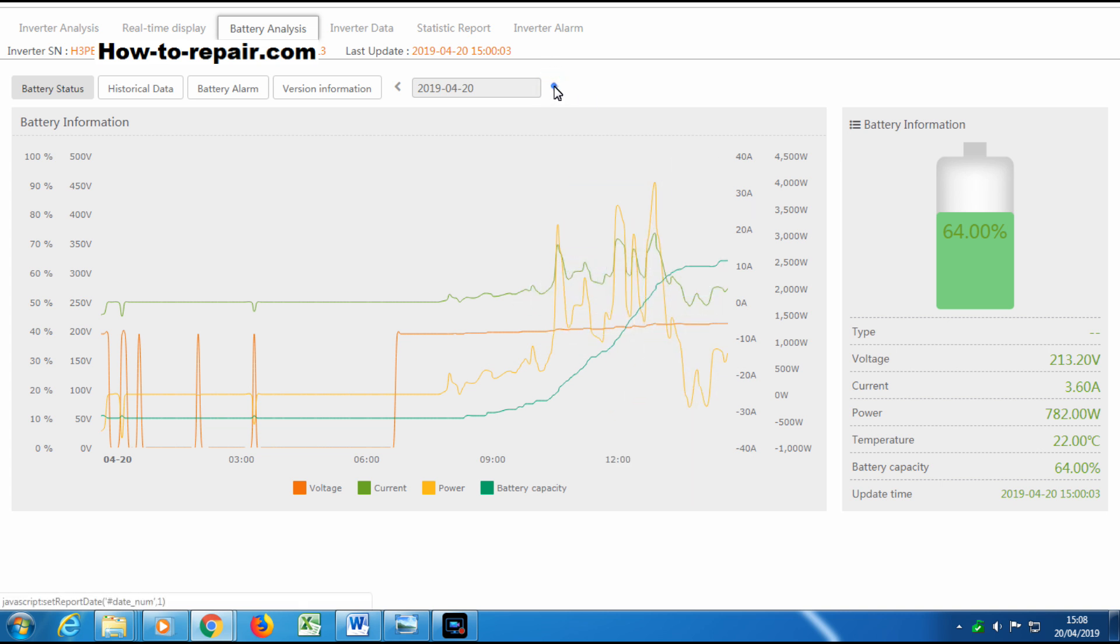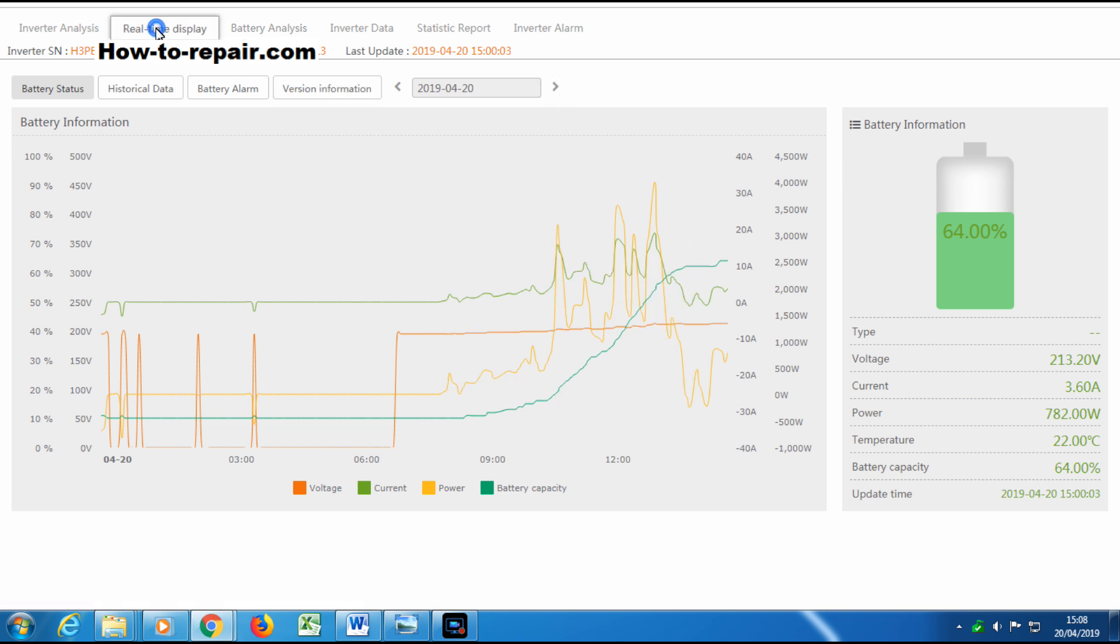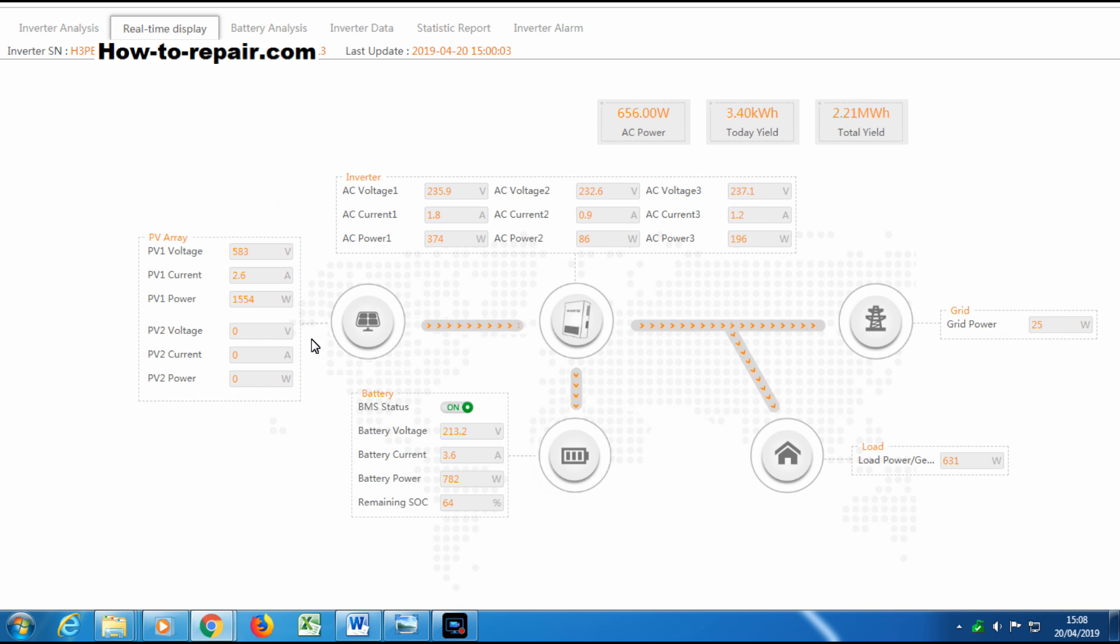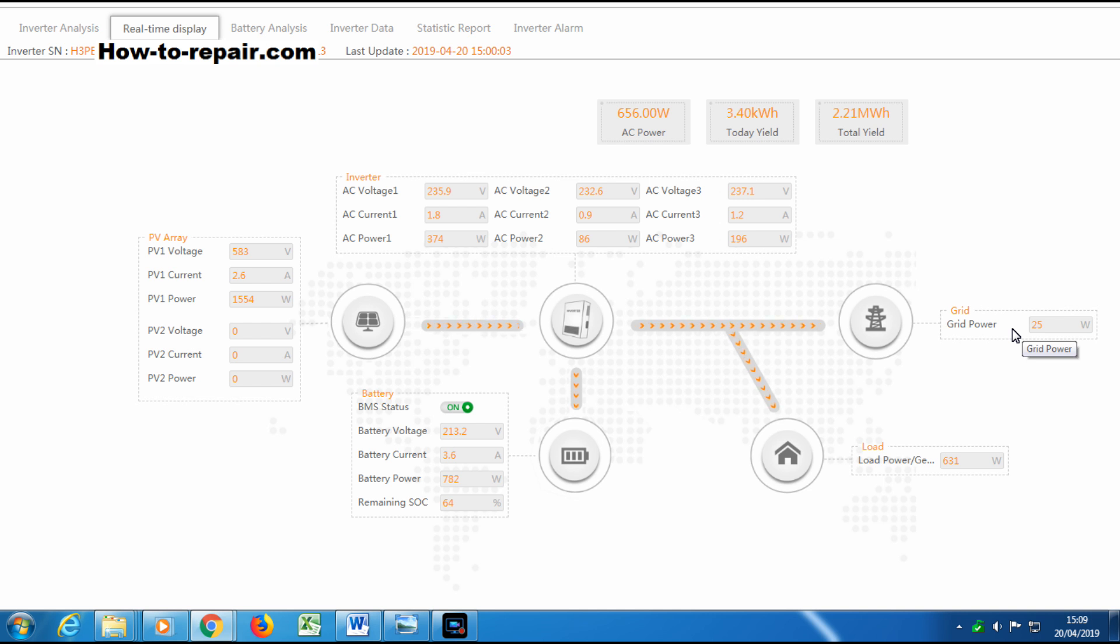Now let's have a look at the real-time graph. This is basically showing us what is happening at the moment. We've got 1500 watts of power going into the inverter where 782 is going to the batteries at the moment, and as you can see we're at 64 percent. The house symbol down below means the property is drawing 600 odd watts of power. The grid power that's showing there, although we are sending some power to the grid, this is to keep the phases balanced so it understands what the electricity supply coming into the building is. We've got ours set at zero, which means we're not exporting to the grid, but it will always stay tied to the grid. This is due to the inverter needing to know the grid voltage and frequency and always stay in sync with the grid.